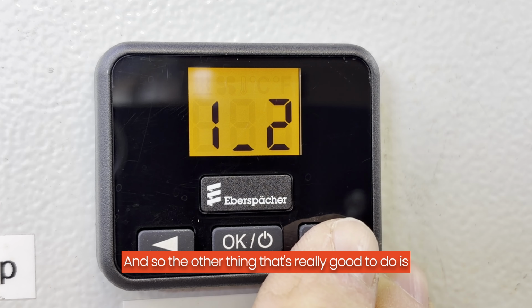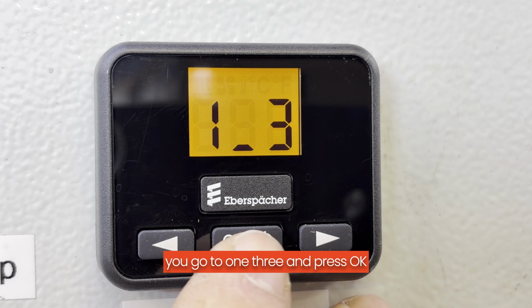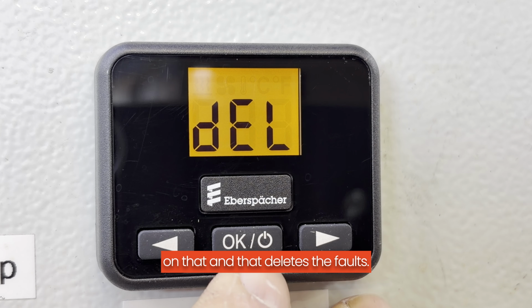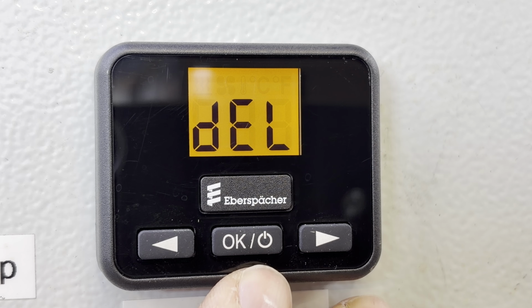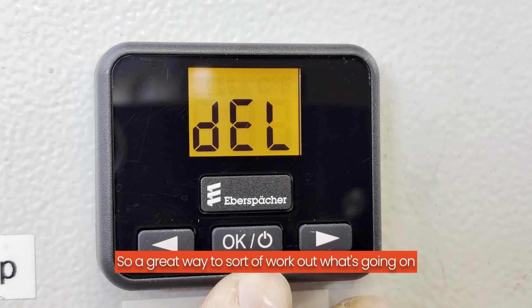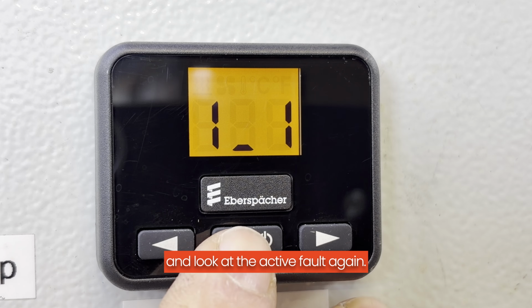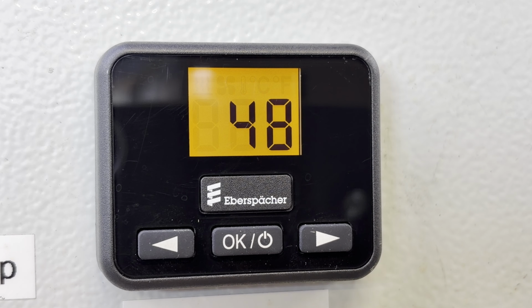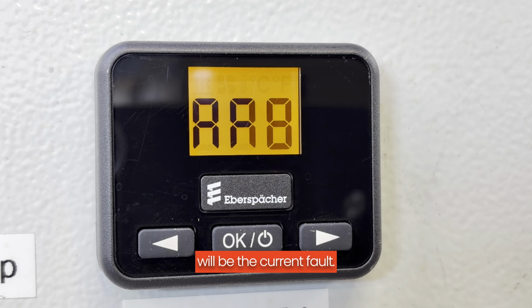And so the other thing that's really good to do is you go to 13 and press OK on that, and that deletes the faults. So a great way to sort of work out what's going on with your heater is to check what fault codes are recorded, go in and delete them, and then go back and look at the active fault again, and the one that's showing will be the current fault.